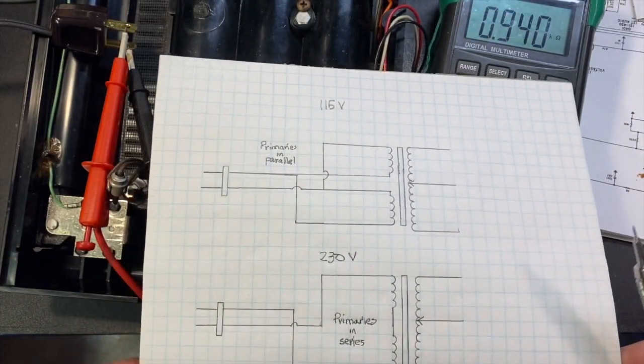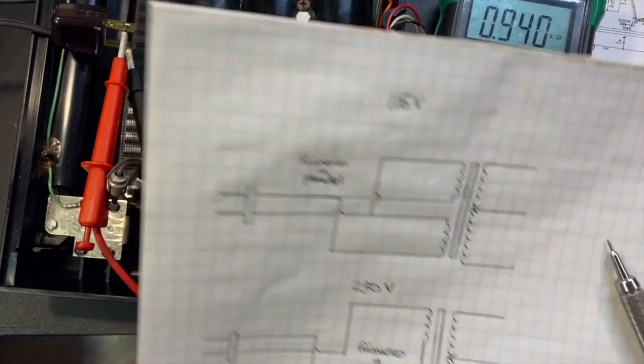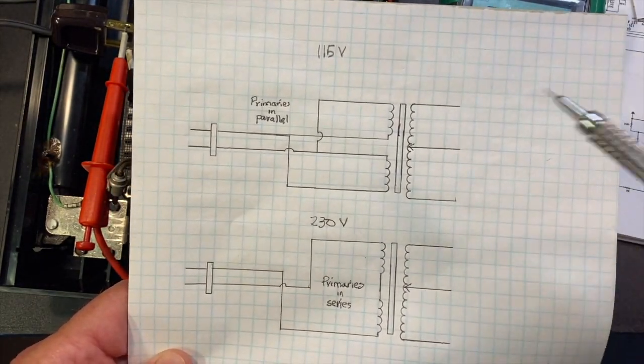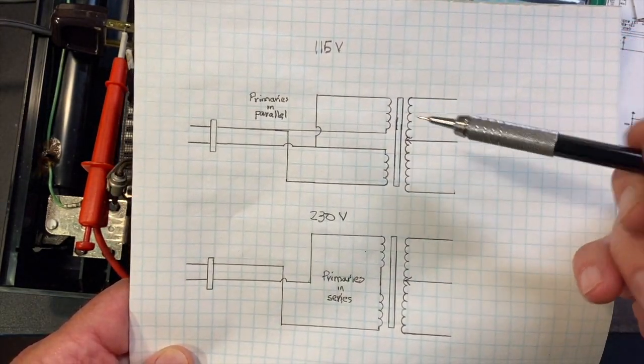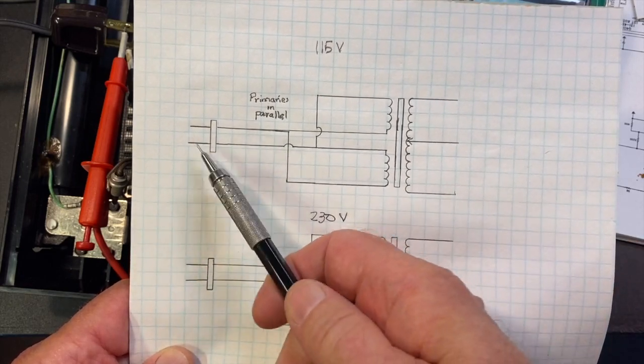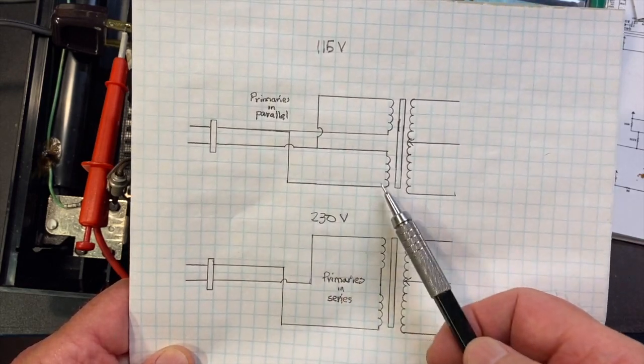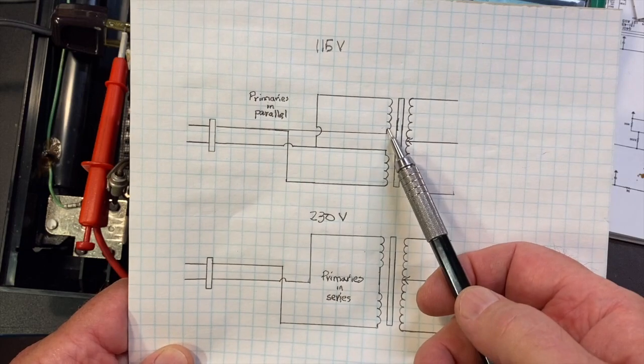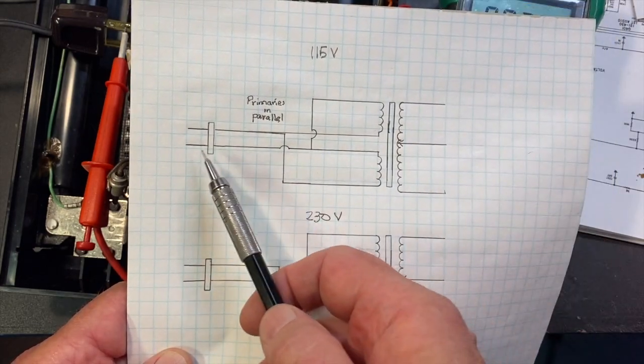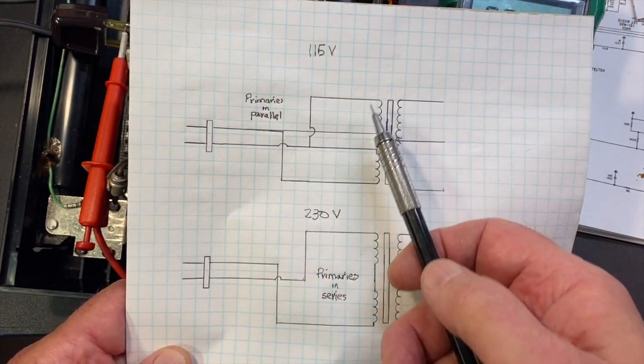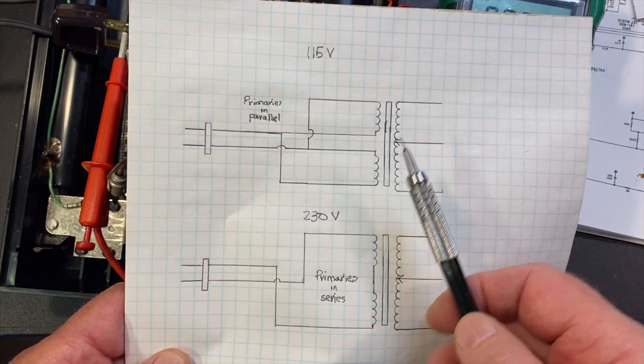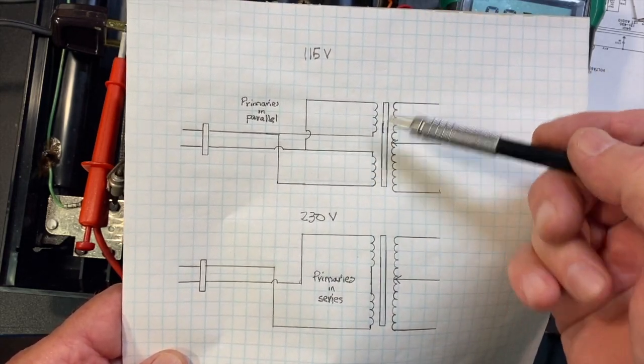This is how the transformer is configured in the 115 volt position. One line comes in, goes to the bottom of one transformer and the bottom of the second transformer. The other line comes in and goes to the top of each of these. That means they're in parallel, each getting 115 volts.